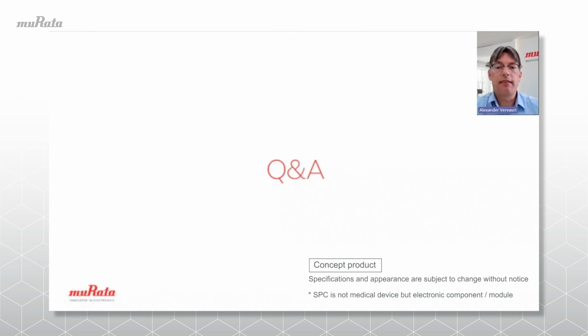What about the biocompatibility of the stretchable printed circuit? The stretchable printed circuit is only a part of the final, total device, so we do ask our customers to do the biocompatibility testing with the complete device. But we have performed internal cytotoxicity testing and saw no notable issues in terms of biocompatibility. So from this point of view, we have done testing to validate the biocompatibility of the stretchable printed circuit.